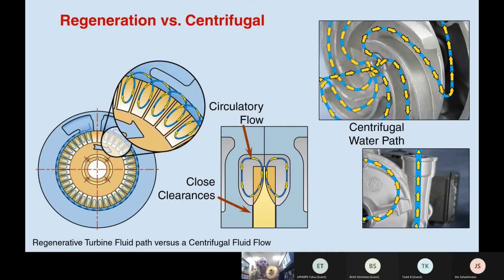And so after it's done this several times and mixed up through the impeller, when it hits the water stop and leaves, it's got a great amount of pressure with very little flow. And so that's the principle behind how the regen turbine works. So if you look at the diagram, you can see that.